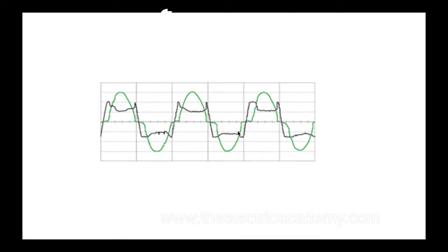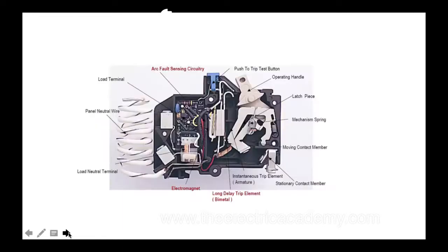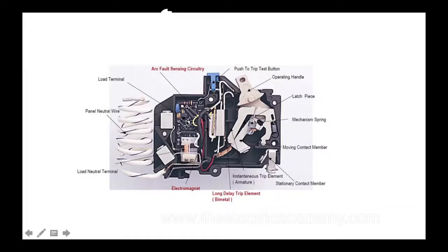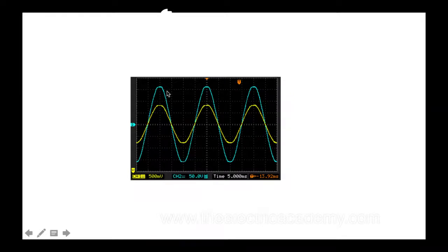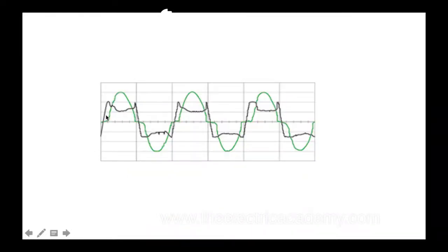So what we need is something that can handle detecting that. Your arc fault circuit interrupter — the AFCI — looks exactly like a GFCI, you've got the breaker and then it ties back to the neutral. But it is very different from a GFCI. A GFCI measures current going in and current going out and trips if there's any difference. This AFCI has a printed circuit board and some have a little microprocessor. They are watching the waveforms — they want to see waveforms looking like the ideal, and as soon as they see something that looks like the arc fault waveform, it trips the breaker. That's what makes them more expensive.